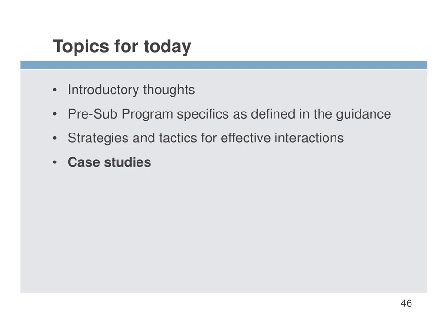If they give you a disapproval letter, then you have a chance to appeal it, and you can kick into a submission issue process. But if the clinical study is a ways away and you know you're going to do something novel in terms of a clinical study, or you want to have an in-depth discussion about the acceptance criteria because there aren't any commonly available, and so you're going to have to go back and forth with them, then the pre-sub may be a good place to do that.